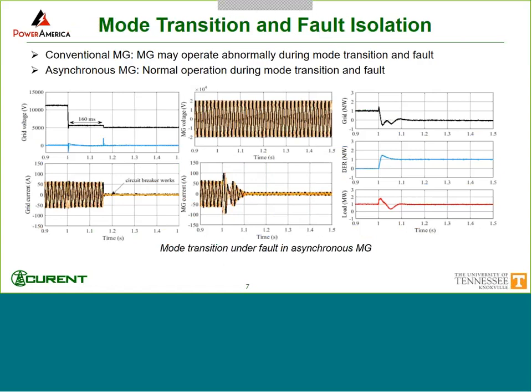And this is the example of mode transition. Let's say there is a fault on the grid side, and you would have to transition to the islanded mode. On the grid side, you will see the voltage start to drop and power start to drop and circuit breakers start to act, but on the microgrid side, you pretty much don't see any changes, and the power will simply transfer from the grid to the distributed energy resources, in this case like energy storage or a backup generator. So that will allow a pretty seamless transition.